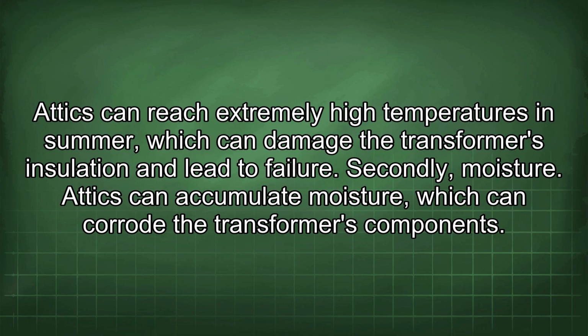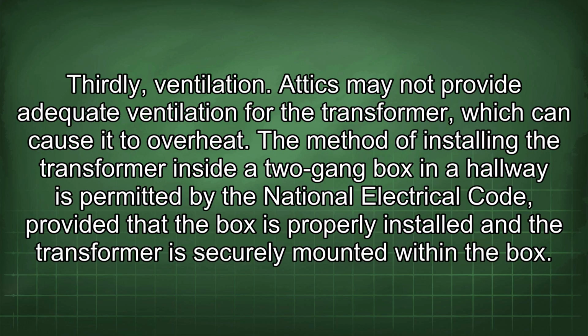failure. Secondly, moisture. Attics can accumulate moisture, which can corrode the transformer's components. Thirdly, ventilation. Attics may not provide adequate ventilation for the transformer, which can cause it to overheat. The method of installing the transformer inside a two-gang box in a hallway is permitted by the National Electrical Code, provided that the box is properly installed and the transformer is securely mounted within the box.